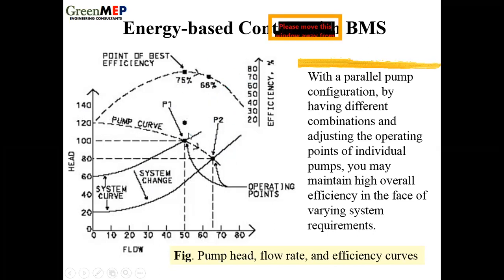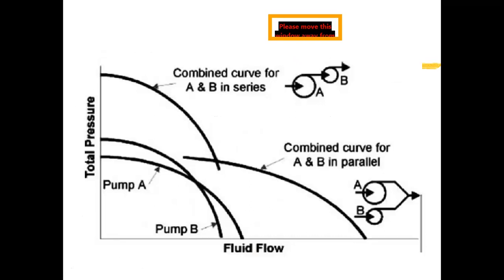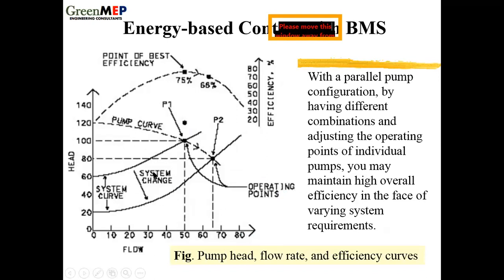You've got to do something. Software has to do something. So what does it do? One of the methods it uses is parallel pumps and series pumps, right? Let's say you have one pump, two pumps. If they are connected in parallel, this is the parallel combination. It's a different curve. If you connect them in series, it shifts this way. The pressure capability increases. This is the series combination of two pumps. Two pumps, individual, series combination, parallel combination. So what you do is, when the system curve changes, you change the pump curve also. And you look for this best operating point, best efficiency point. That's what the software does, right?